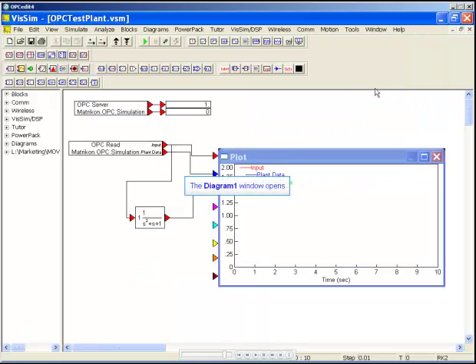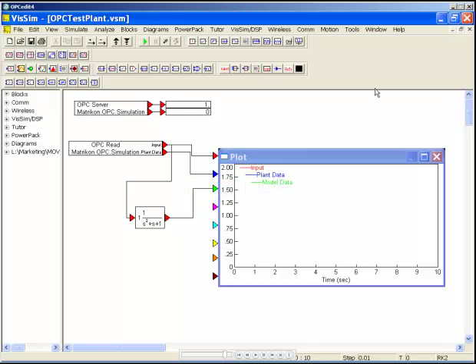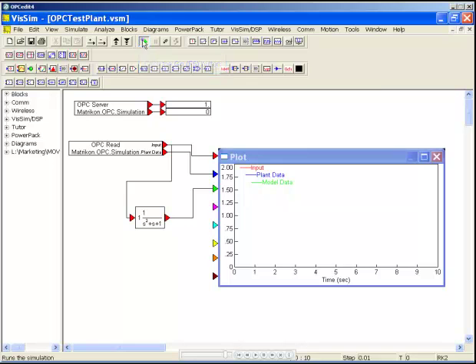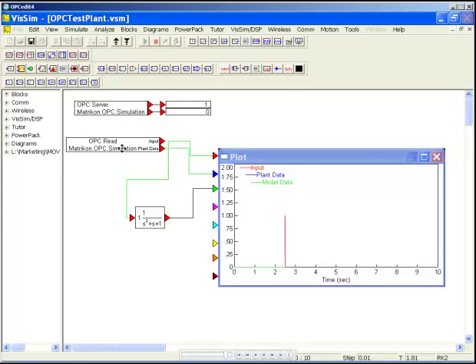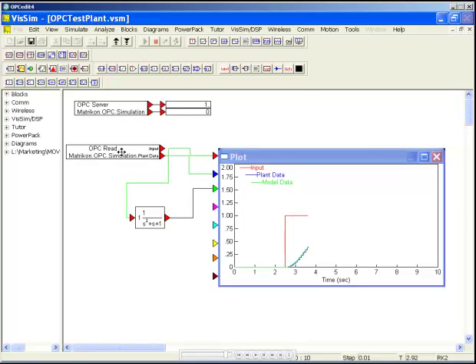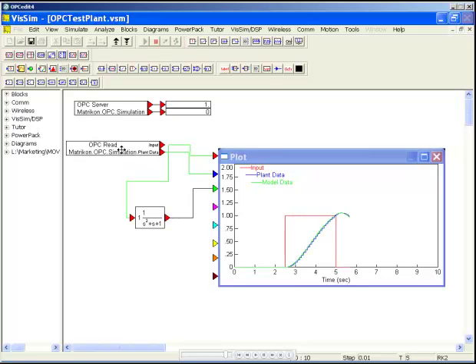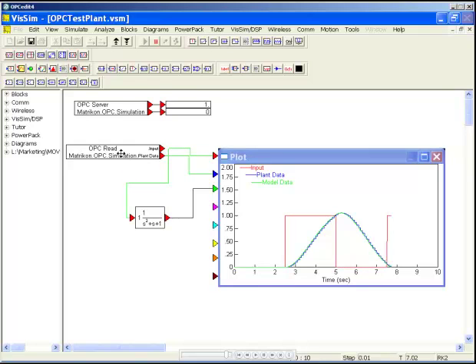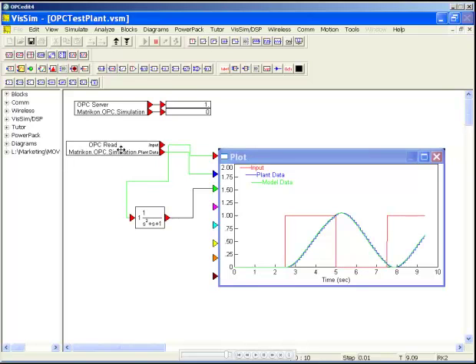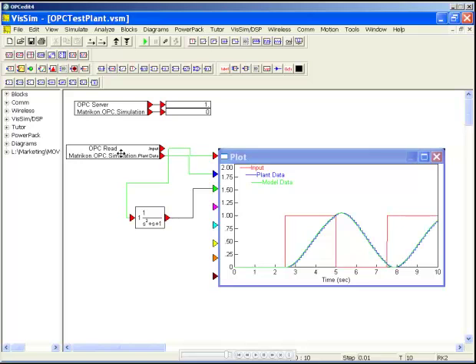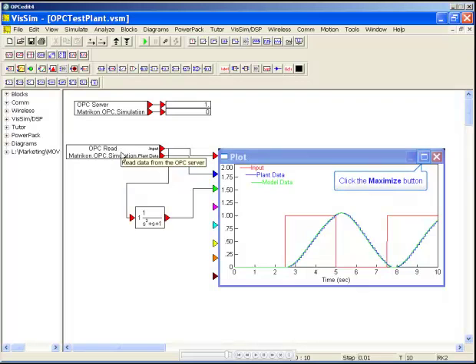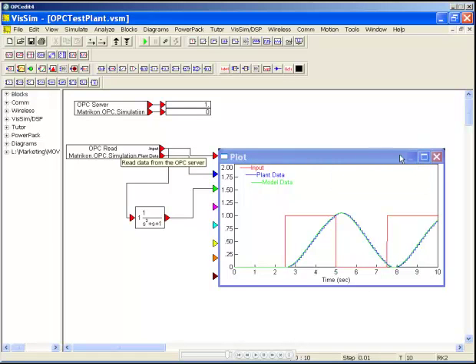Now we can look at how we can validate a plant model. In this case, we can read some plant data from a server and see if our model produces a similar result. From the plant, we will plot an input disturbance and the plant reaction. We can use the same input disturbance to feed our plant model. We can say the model is accurate if the output data match up.